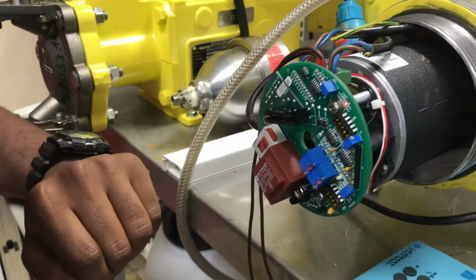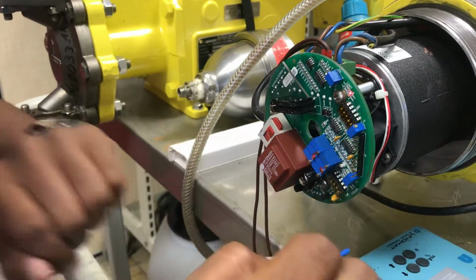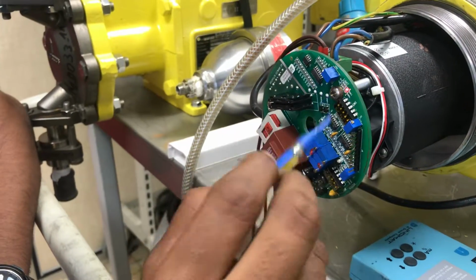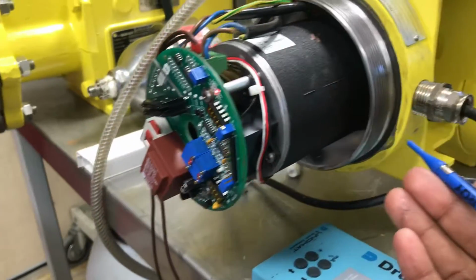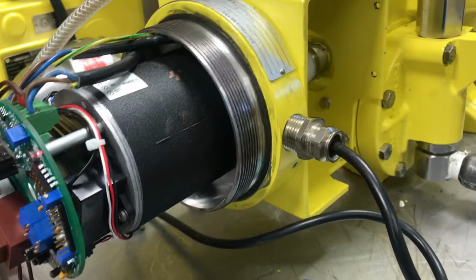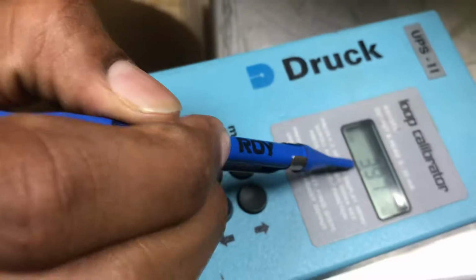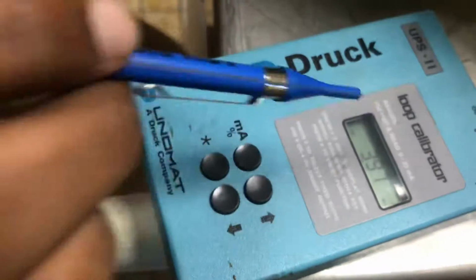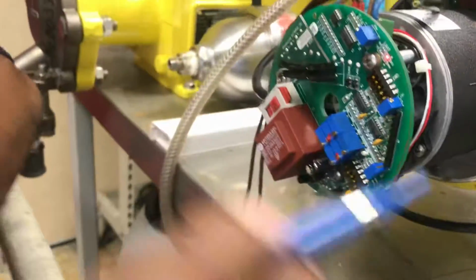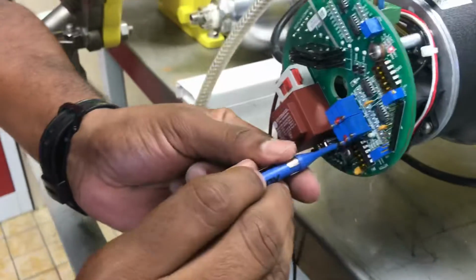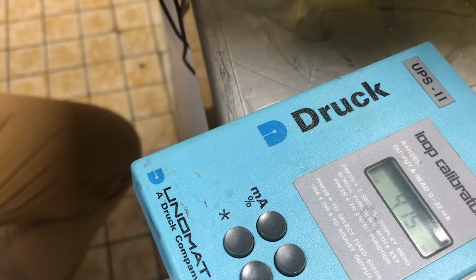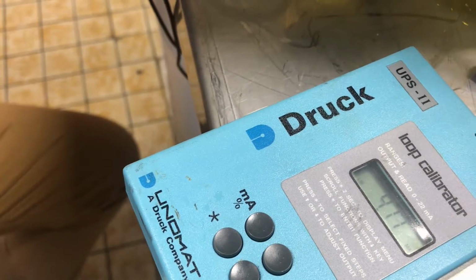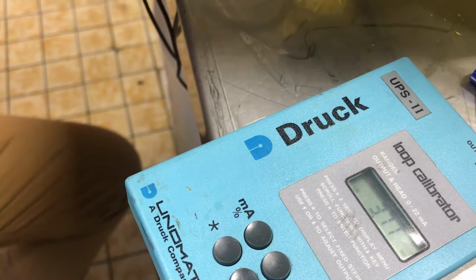Now you have to check the signal cable, the signal meter. Now you have to give 4 milliamps, and it will check from 20 milliamps to 4 milliamps how many rotations are coming. Since we adjusted, it will come 10 turns, and here you have to check the feedback whether it is 4 milliamps or not. Here 3.97, it's almost 4 milliamps. To adjust this, this is the lower limit, so the left side is the lower limit. See, now I am adjusting the feedback. Yes, very slowly.